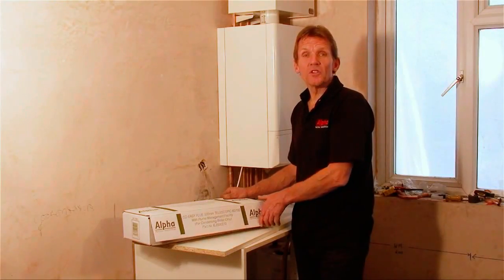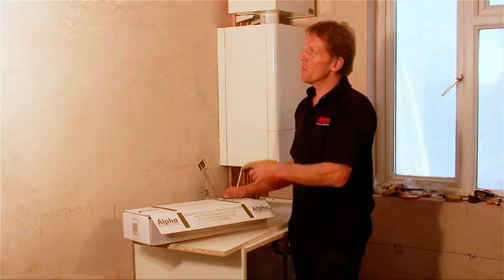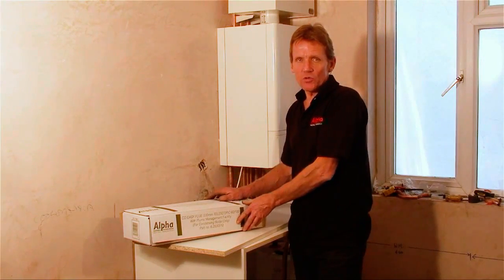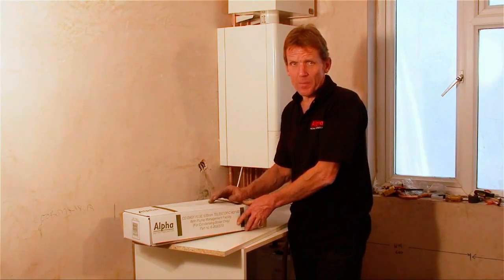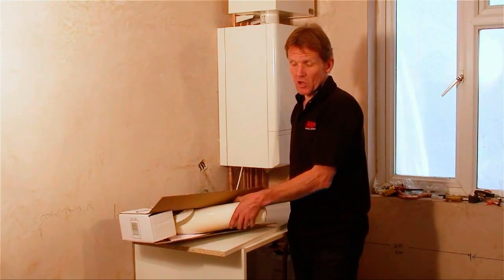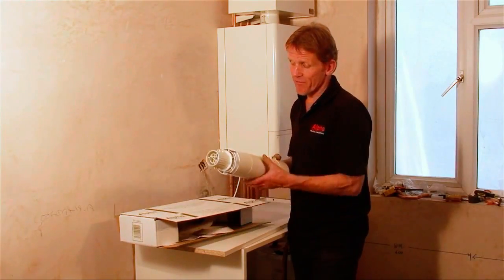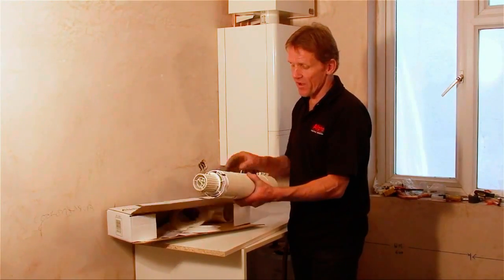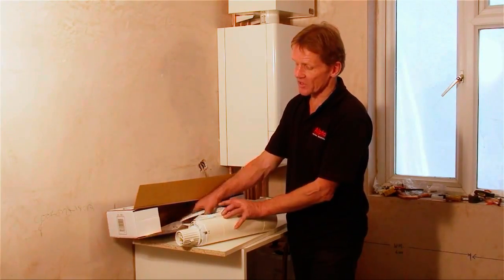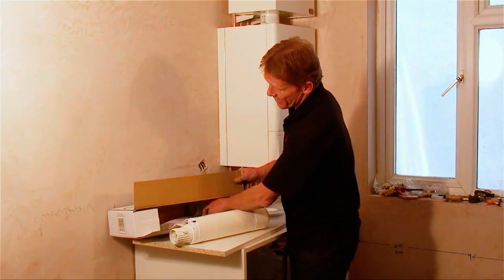With Alpha boilers, you get all the usual fluing options. But because this is a straightforward installation with the flue coming out to the right-hand side, all we need to use is the Easy Flue Telescopic Kit. This comes in 500 millimetre and one metre options, giving you a lot of flexibility even from this standard flue. In this case we have the 500 millimetre telescopic flue, and you get the internal and external sealing rings, and also the 90 degree elbow.